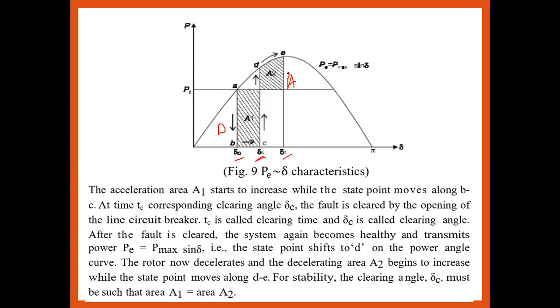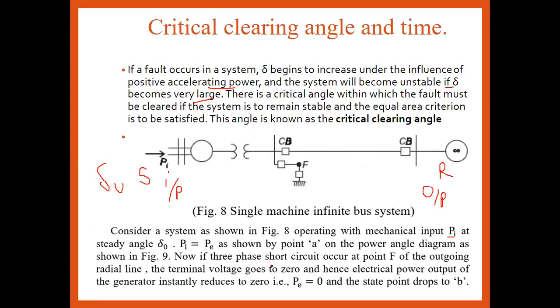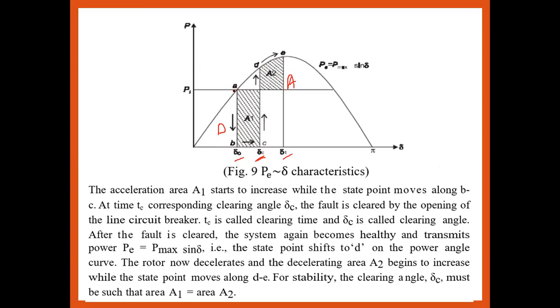With the fault on the system at the point where it occurs on the radial system, the terminal voltage goes to zero, hence the electrical power output also goes to zero. So Pe equals zero. At the initial condition, the system is running such that power equals Pi or Pm at delta-zero — that is from A to B. With fault on, power equals zero. At a particular value of delta — that is delta-c — the fault is cleared.